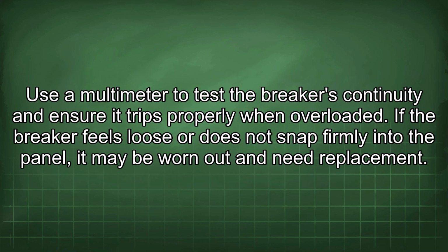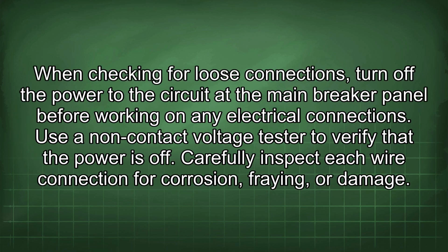Use a multimeter to test the breaker's continuity and ensure it trips properly when overloaded. If the breaker feels loose or does not snap firmly into the panel, it may be worn out and need a replacement. When checking for loose connections, turn off the power to the circuit at the main breaker panel before working on any electrical connections.